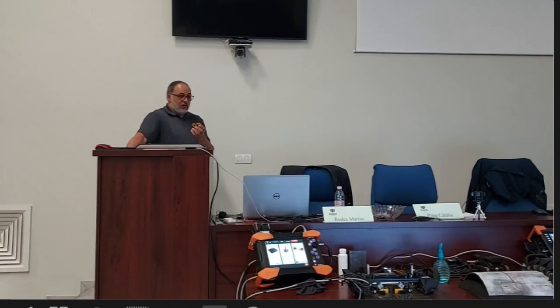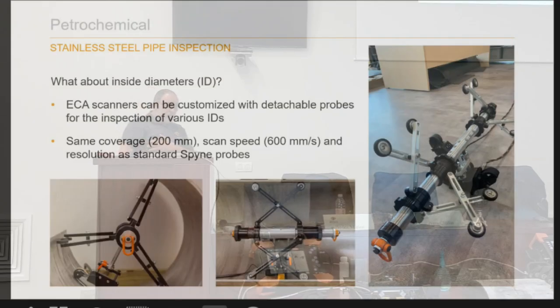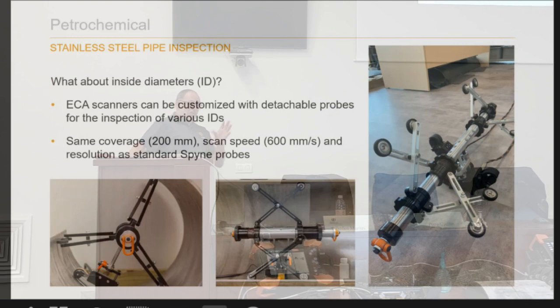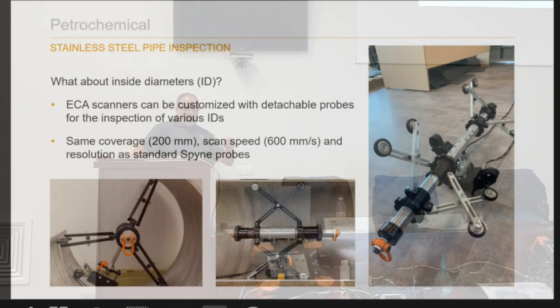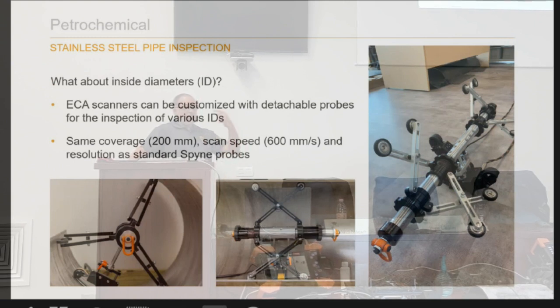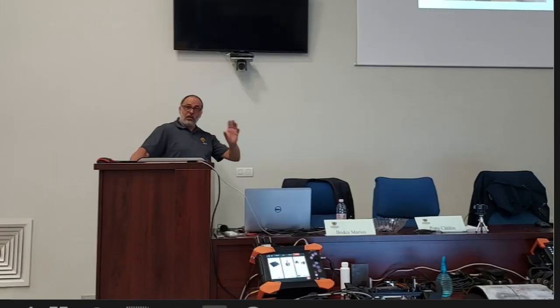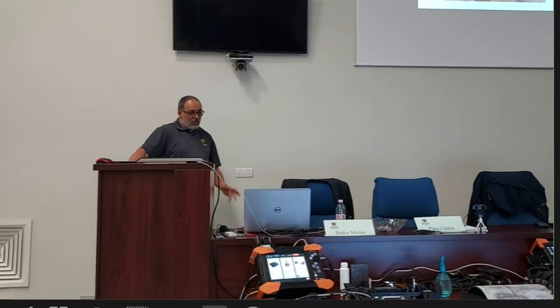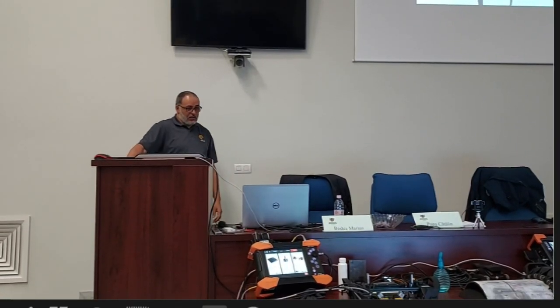An example of internal inspection required. We developed in-house this scanner that can adapt to a range of diameters, with one single Eddy Current Array probe able to rotate 360 degrees. You can do several passes to complete your inspection. This is meant for straight tubes, not elbows - elbows are a bit more complicated to pass.